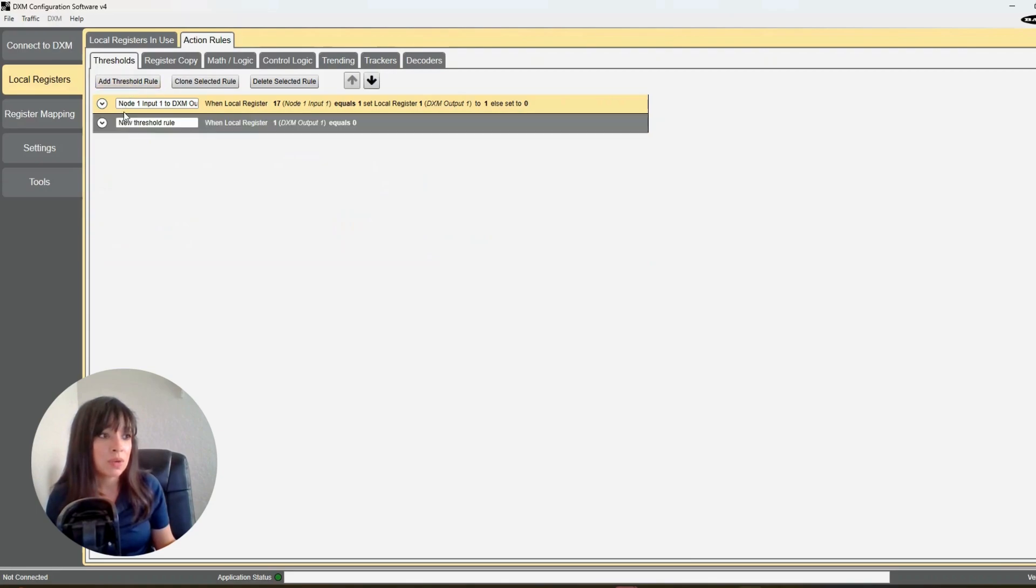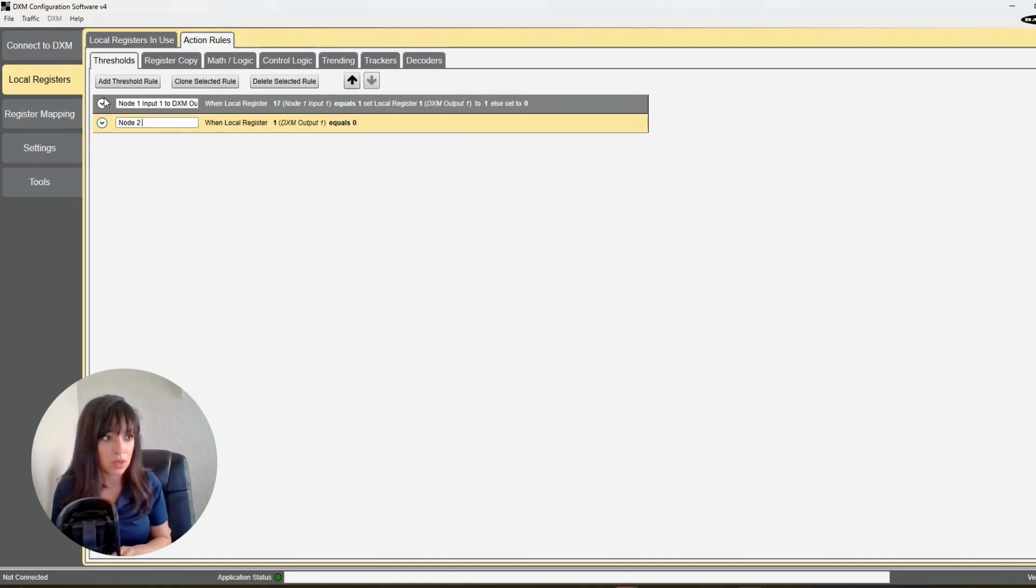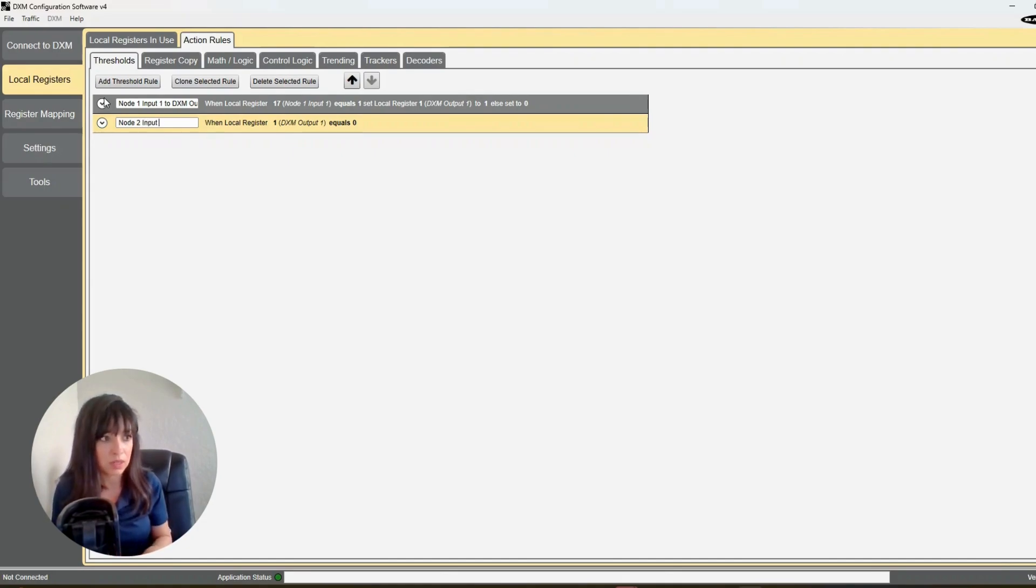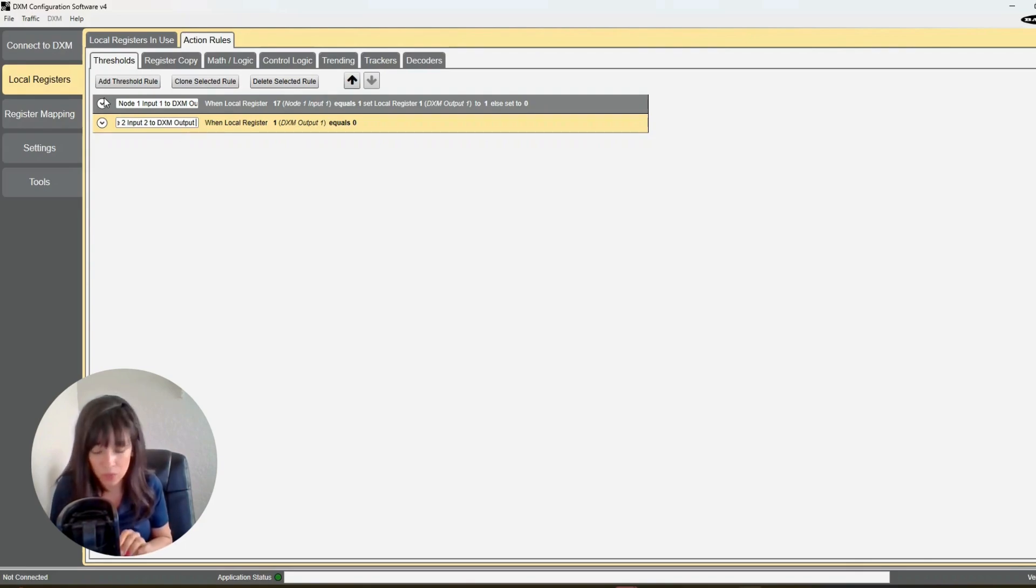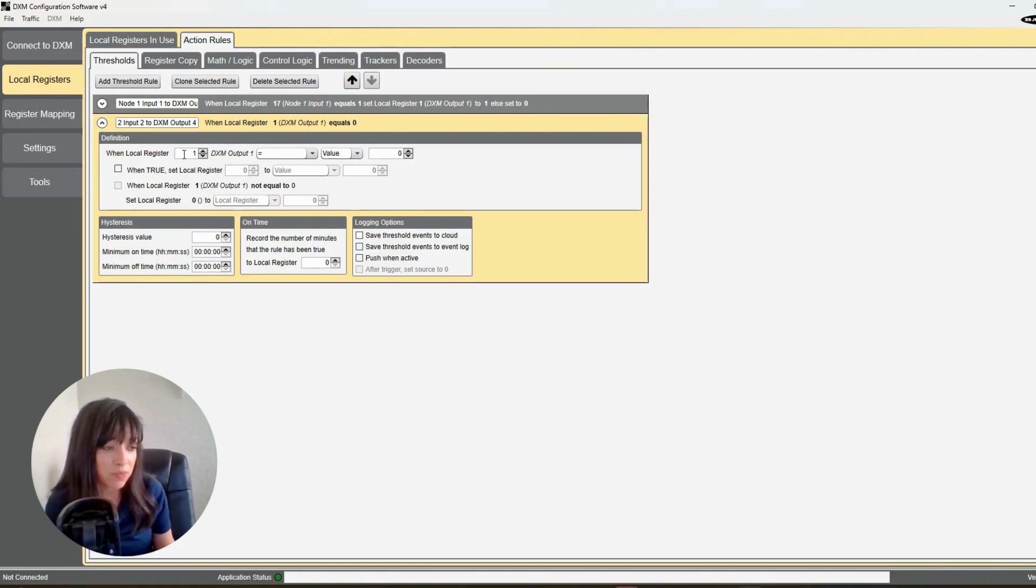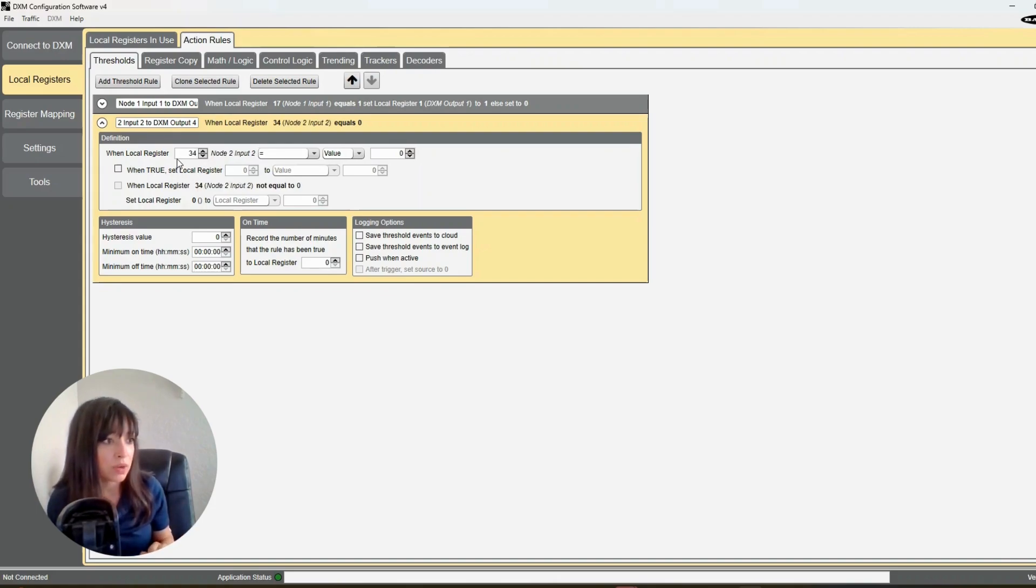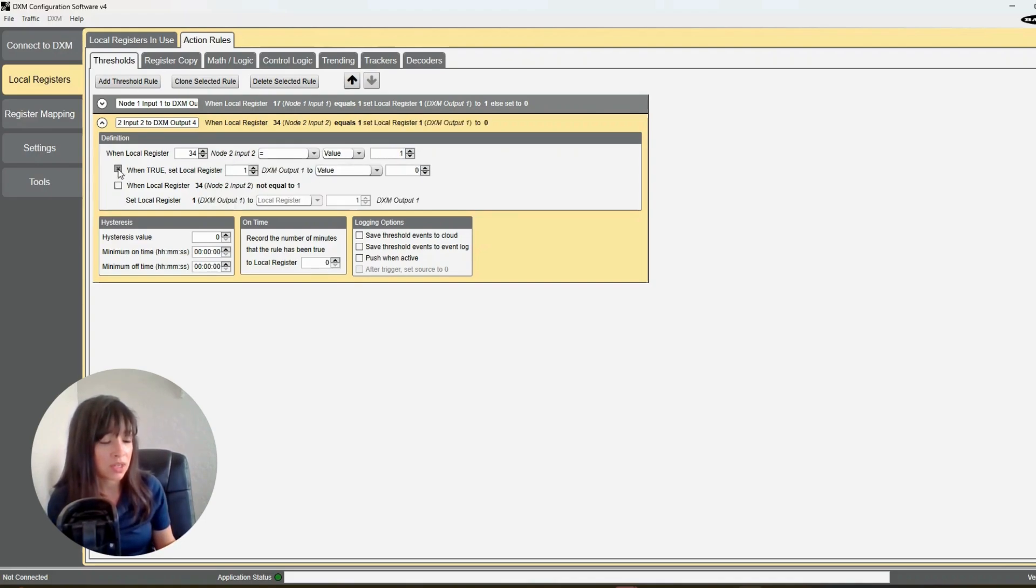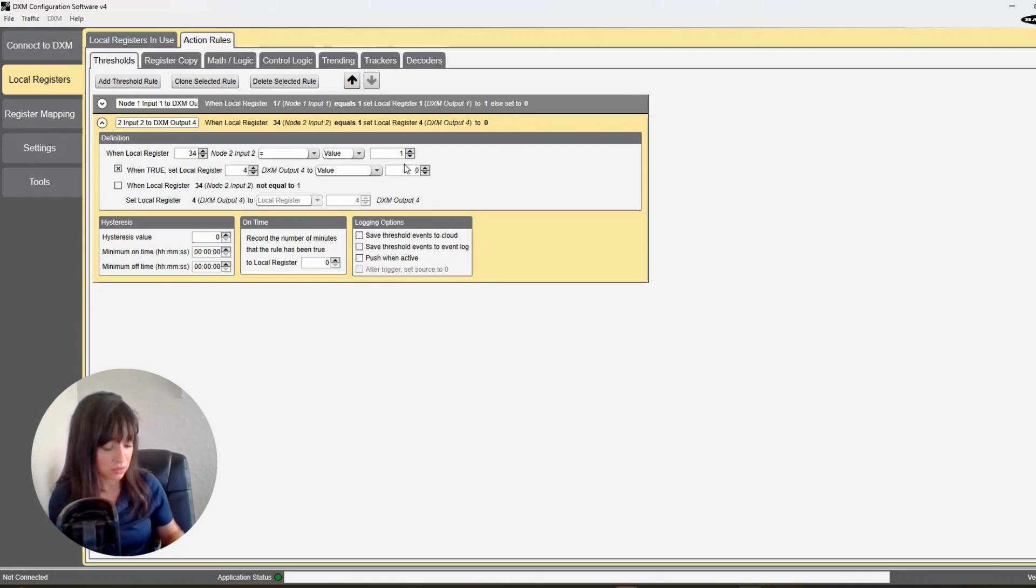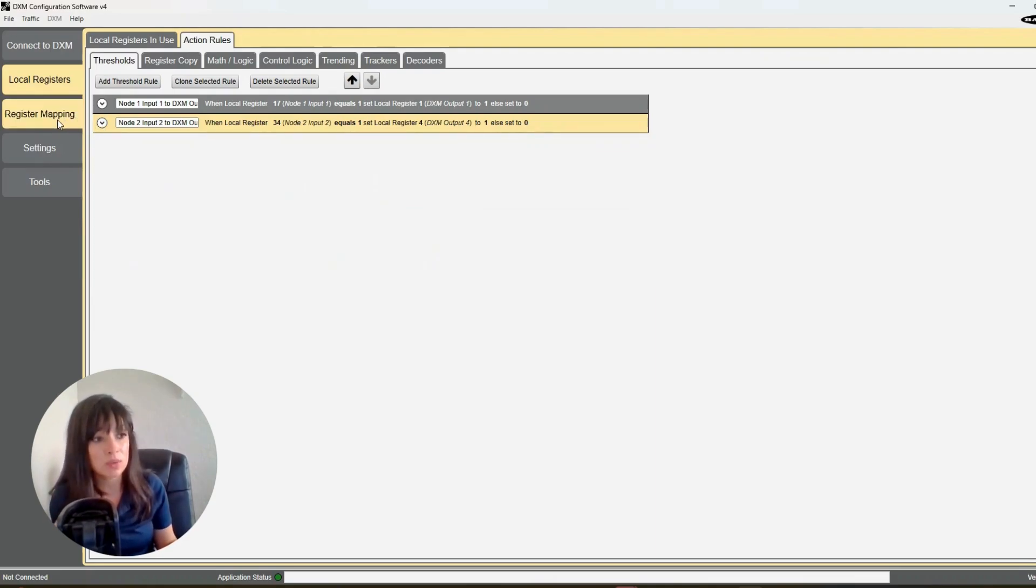We're going to make a new rule now. We want to do node 2 input 2, I'm sorry, node 2 input 2 to DXM output 4, okay? I know this is getting a little—this is what is wired up, so we're just going to make it match. So now we're going to say we're on—it should be 34. Yep, node 2 input 2 equals—when that is equal to 1, when that turns on, check that box. I'm going to turn on output 4 to on. And then when it is not on, set it to 0. And that's it. That's what we want the logic to do.